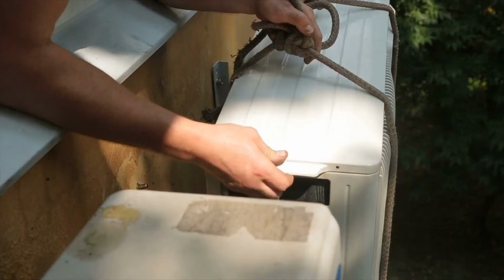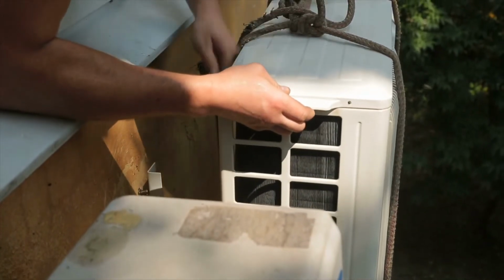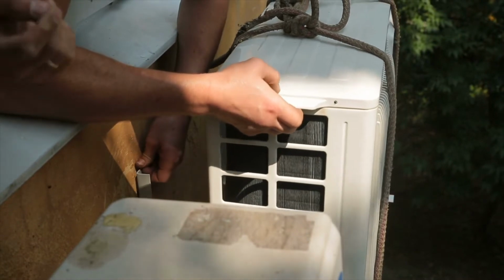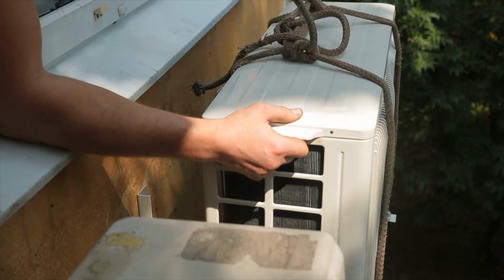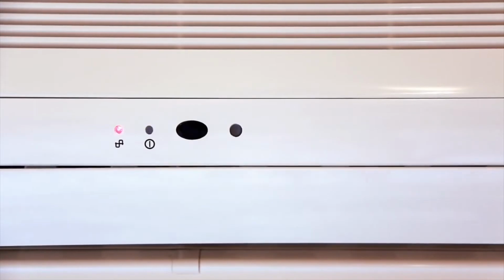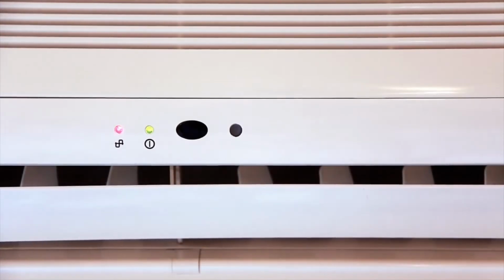Heating functionality. Another great thing about ductless systems is some models can also provide heat in the winter. Ductless systems are essentially a type of heat pump, which means they can technically be run in reverse even in cold weather. Not all models are capable of this, but for some homes and in certain climates, this can be a feasible heating option for most of the colder months. It's also worth noting that the heating functionality typically becomes less effective in extremely cold temperatures, below about -15 degrees Celsius. So a supplementary heating system may be needed for certain stretches of the winter, depending on where you live.